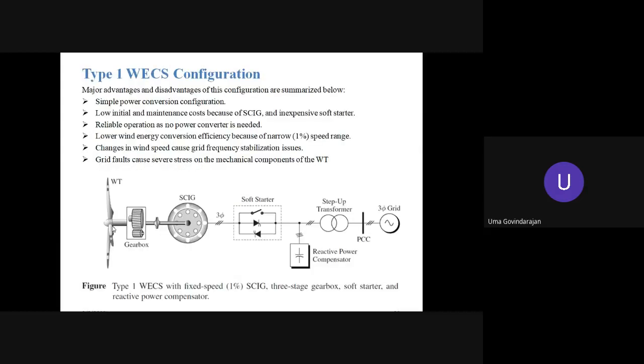Well, let's look into the architecture of each of these configurations. What are the different building blocks of each of these? The major advantages and disadvantages of the type 1 configuration are provided below. So we have type 1, a fixed speed turbine, whose generator is a squirrel cage induction generator, and we have a soft starter to limit the inrush current, and it is directly connected to the step-up transformer to the grid. So it does not involve any power converter.